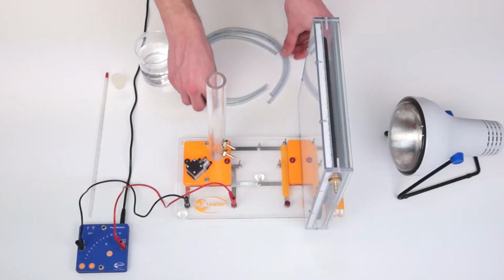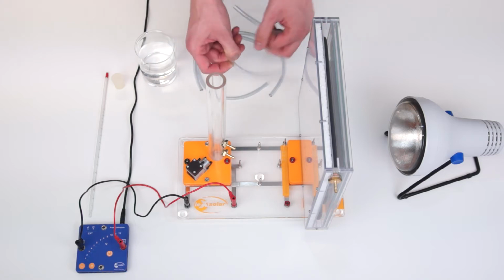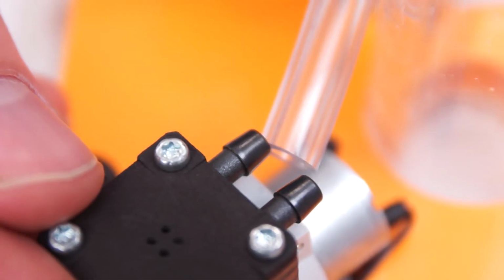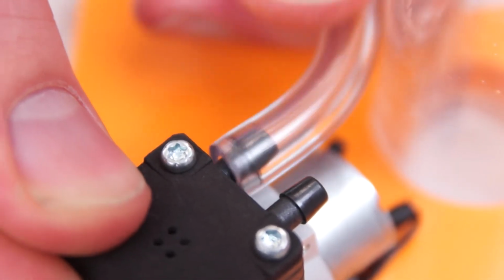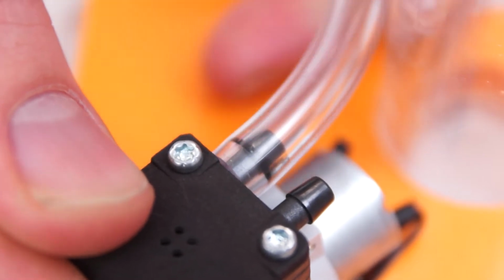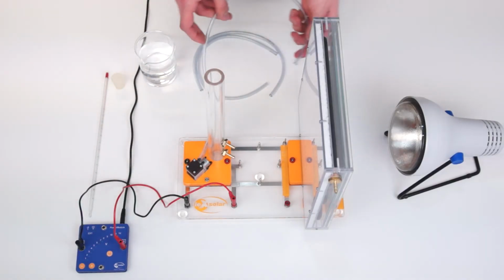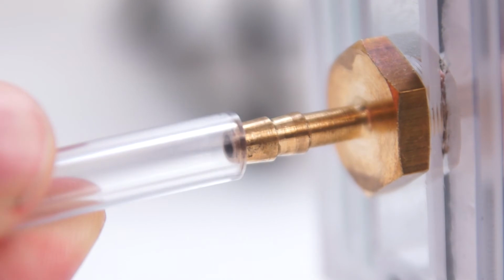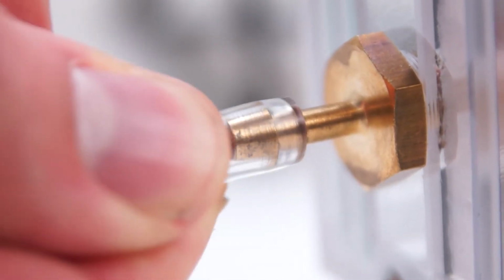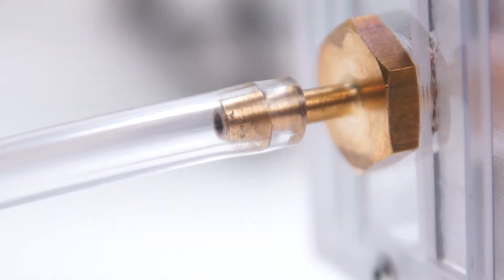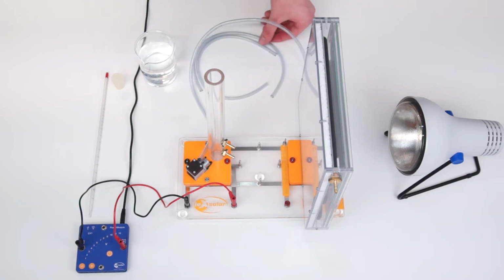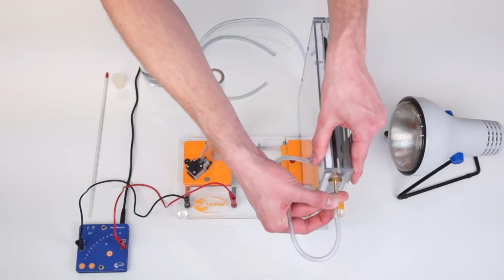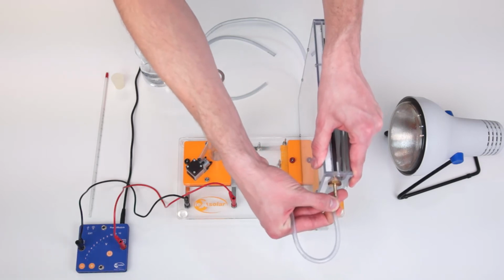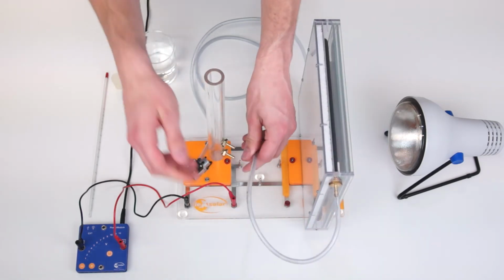Now we have to connect the components with each other through the tubes. It's important to note here that the right connection of the pump is the pump output, and this is connected to the lower hose input on the collector. This best ensures that during subsequent pumping, no air is left in the water cycle. The upper connection of the solar collector is then connected to the upper port on the balancing container.